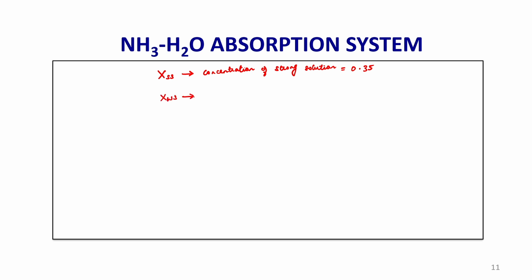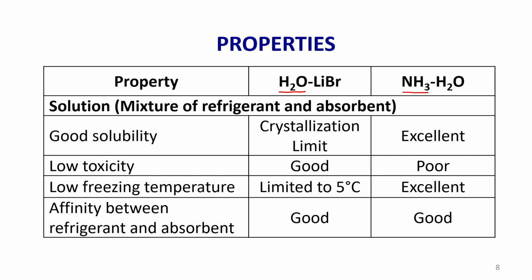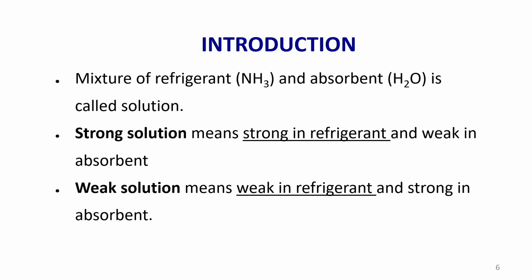XWS is the concentration of weak solution. When I say strong solution, the refrigerant quantity is more compared to the weak solution. When I say weak solution, the refrigerant quantity is less. So remember this slide: strong solution is strong in refrigerant, weak solution is weak in refrigerant.